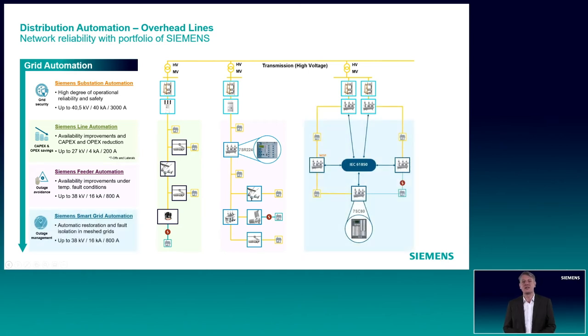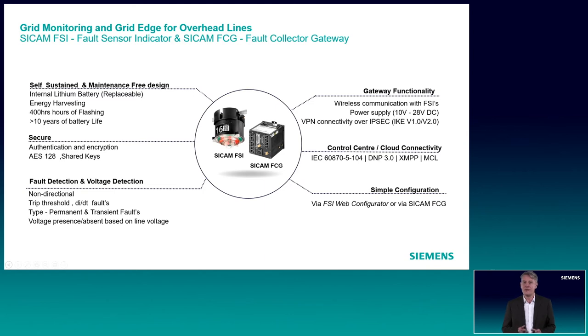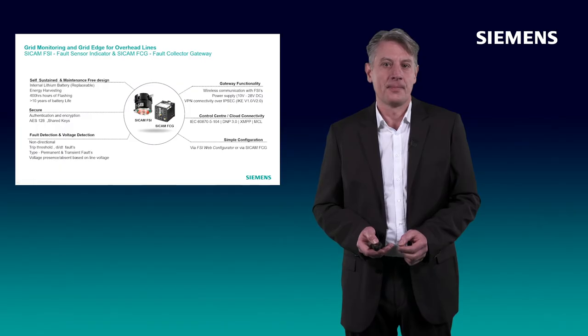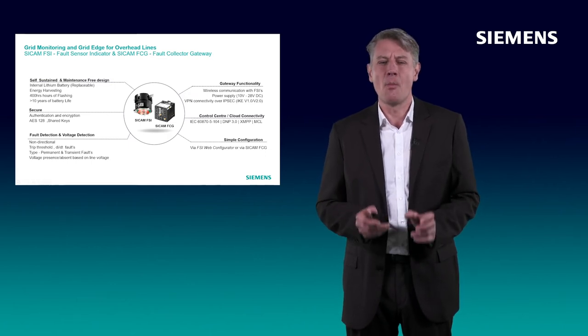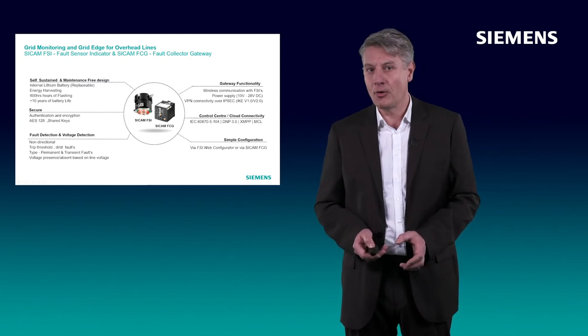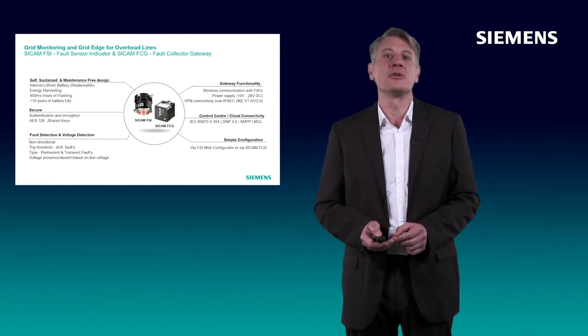The third architecture is the smart grid architecture, based on new protocols, new functions, and new applications — for example, IEC 61850. Let's focus first on the first pillar, on the grid monitoring and edge devices for overhead lines. We have a combination of SICAM FSI and SICAM FCG. These devices are directly mounted on the overhead lines and communicate via the SICAM FCG fault collector gateway to the cloud. This functionality is primarily there for monitoring short circuits, earth faults, and the overhead line to get an indication of where the fault is located.